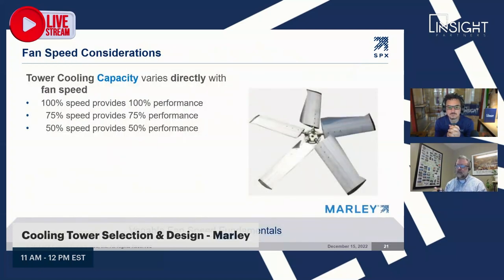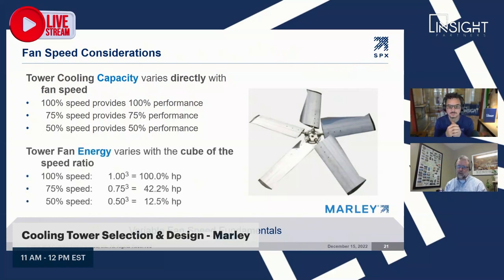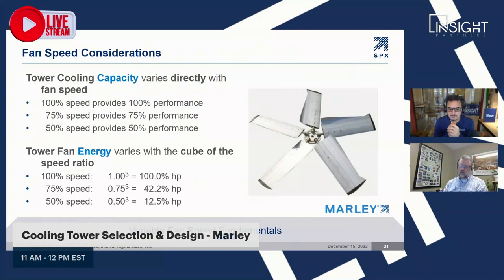From a system optimization energy standpoint, when we use a VFD and slow the fans down roughly 50% fan speed, we still provide 50% performance. The big benefit is that at 50% speed, you're only using one-eighth of the horsepower — big energy savings. VFDs are widely accepted and used on a majority of projects today. Additional benefits include mechanical equipment lasting longer, and significant sound reductions since the fan ramps up and down rather than switching on and off abruptly.